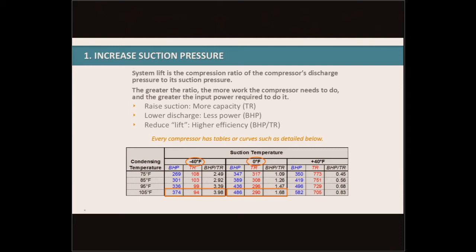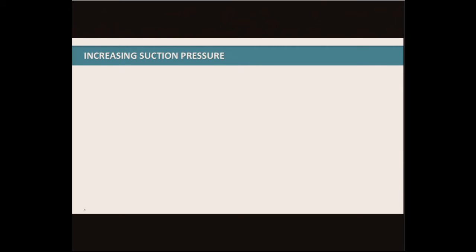When we look at adjusting the suction pressure, we're going to do it incrementally. If we're at a zero pound suction pressure, we want to see if we can go up to two or four pounds. The rule of thumb for calculating savings: there's about a 2% compressor efficiency gain per degree Fahrenheit increase in suction temperature — not per pound increase, but per degree Fahrenheit increase.